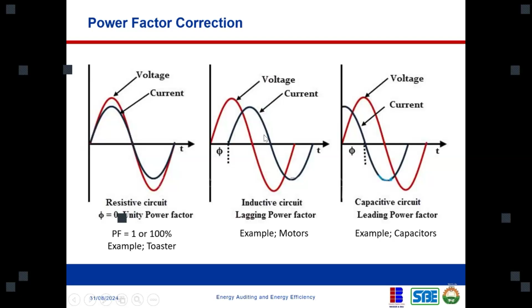I've already explained this before. This is a resistive load where voltage and current are in perfect harmony, there's no power factor issue here. But when you have an inductive load, there's a displacement. To correct this displacement, you need a capacitor bank, which is a capacitive circuit. When you combine this second chart with the first, you come back to perfect harmony, and that's why in power factor correction we use a capacitor bank to correct power factor.